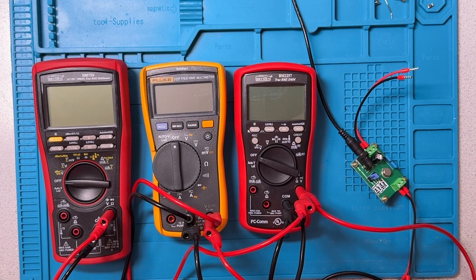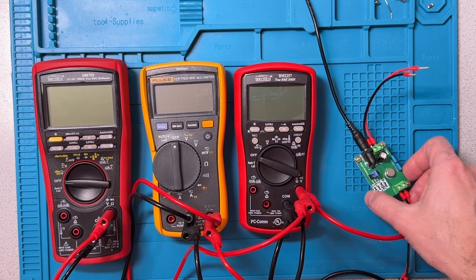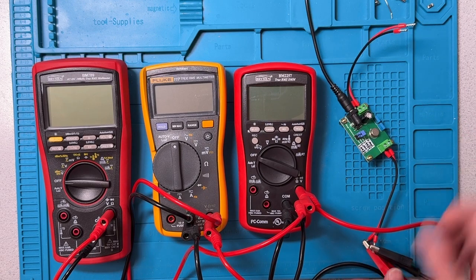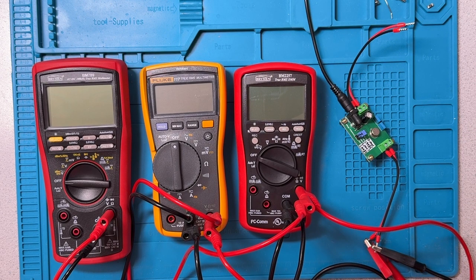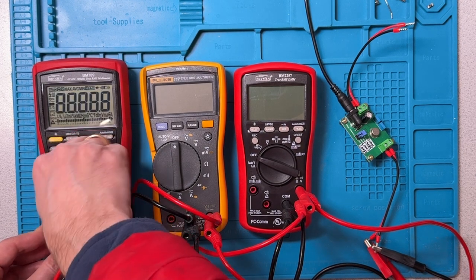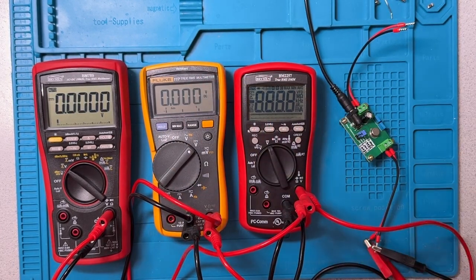And that's what I'm doing here for DC voltage. So I've got a voltage reference source here, and the reference, the calibrated reference values will be in the overlay. Now let's turn all of these on to DC voltage. So we've got DC voltage across the board, and good thing they're all reading 0 because it's not turned on yet.